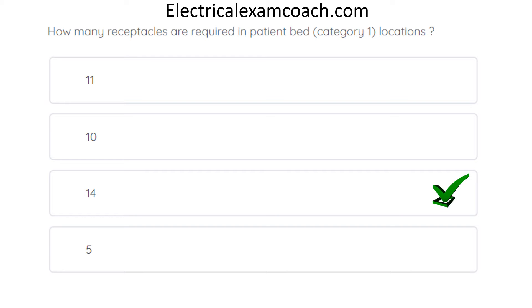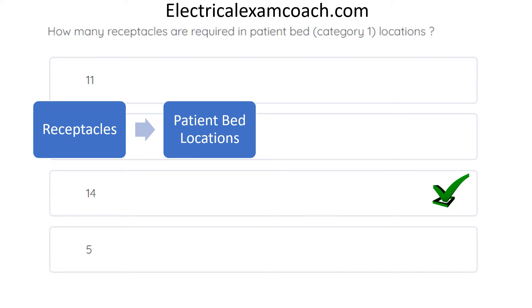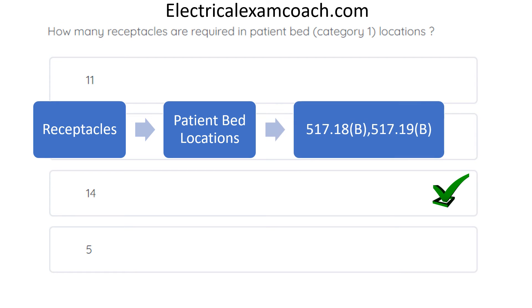There are 14 required receptacles in a Category 1 patient bed location. To find it, we use our keyword and index process. We go to R in the index for receptacles, then look for more keywords — specifically patient bed areas. We look up patient bed locations in the index, and we find two code references: 517.18(b) and 517.19(b). We flip there and use our bold headings to navigate — the first reference is Category 2, so we move to the next bold heading, which is Category 1. When we read that paragraph, we find that 14 receptacles are required.